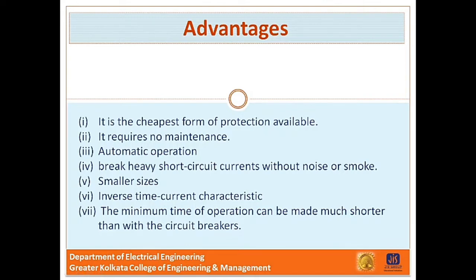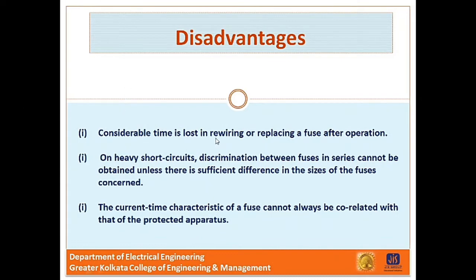But it has several disadvantages. First, considerable time is lost in rewiring or replacing a fuse after operation — whenever overload or short circuit occurs, we have to replace the fuse material, which is a problem. Second, on a heavy short circuit, discrimination between fuses in series cannot be obtained unless there is sufficient difference in the size of the fuses concerned. And last, the current-time characteristics of a fuse cannot always be correlated with that of the protected apparatus. Sometimes we need an instantaneous disconnecting device, but since a fuse has inverse characteristics, for small currents it takes a long time.